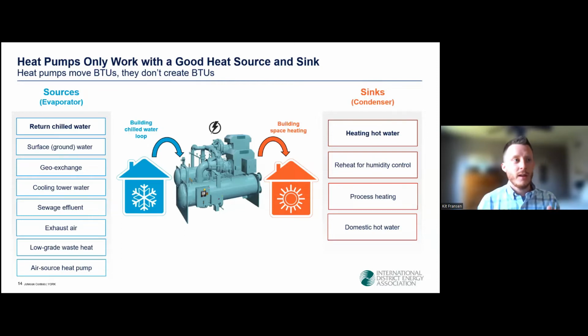You can see in this list on the left-hand side there are many sources from which a heat pump can extract heat, and the available heat can be used for many purposes, from direct space heating to reheat, domestic hot water, and process heating. Once again, any installation where you've got an adequate source and a sink that coexist together may be a valid application for a heat pump. And lastly, the lowest hanging fruit is leveraging the return chilled water and using that for heating hot water.